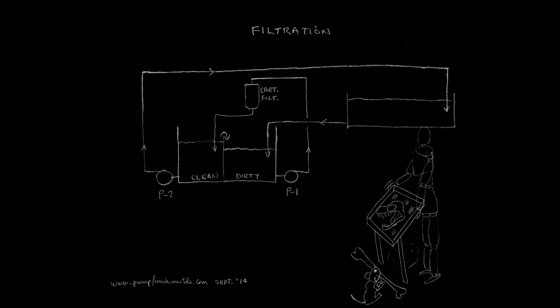There are two water levels to control. If we let the clean side overflow into the dirty side, this will control the level of the clean side. This strategy of controlling the level by letting a tank overflow is simple and effective, and is used in many different types of industrial processes.